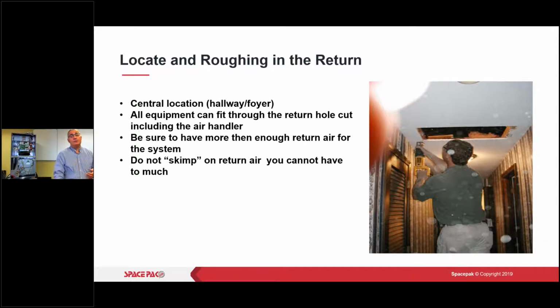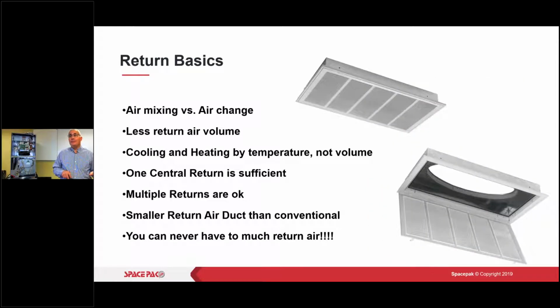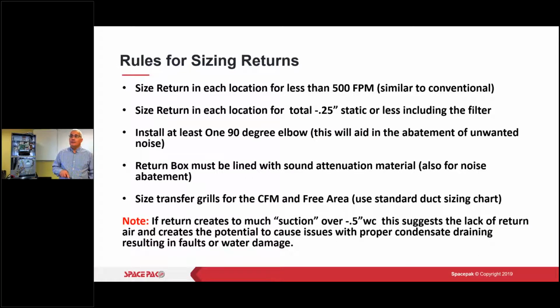But you want to use our return box, and if possible, use our filters. So it's air mixing versus air change, so it's less return air volume. Okay. So we are cooling by temperature, not by volume. 1 central return is going to do you fine. But again, if you want to add more, you can. So we want to size it in each location for less than 500 feet per minute. Okay.